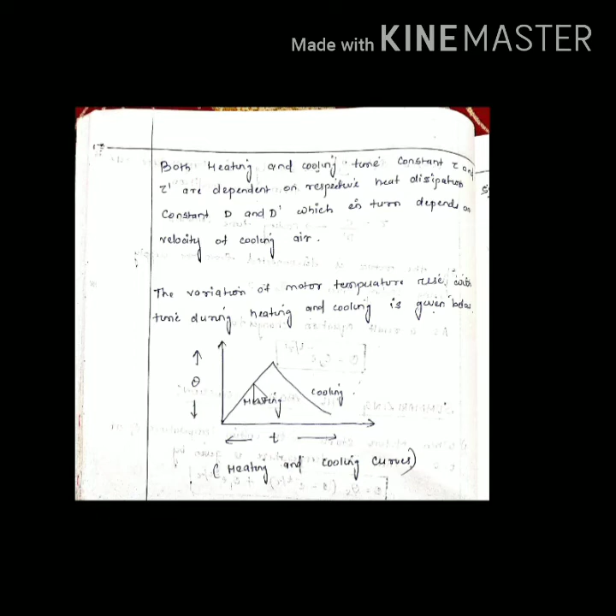It must be noted that for periodic load, the temperature at the end of the cycle will be the same as that of the beginning of the cycle. So if I extend this curve, I will get something like this up to 40. So when I go to this 20 value, please note that 20 should actually be 30. So if I extend this line here, I will get 30 minutes. So the graph for cooling will go like this up to 30 minutes and the temperature will be 40. For periodic load, the temperature at the end of the cycle is the same as at the beginning of the cycle, that is 40.